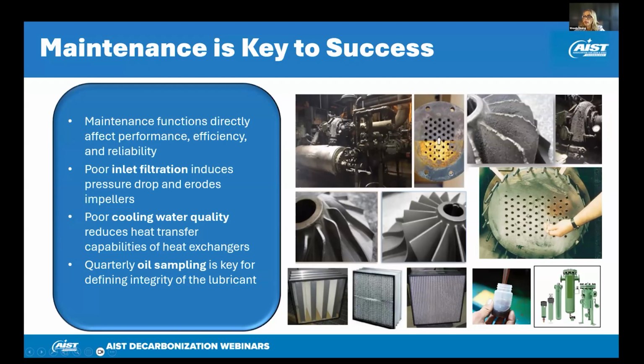In addition to that, another key component for maintenance to improve reliability and reduce power is cooler maintenance. We have a shell and tube style cooler here. If you don't have good cooling water quality, what's going to happen? You're going to get scaling, you're going to get fouling and sediment in the tubes. And again, the coolers are not going to be able to perform how they were designed to perform.